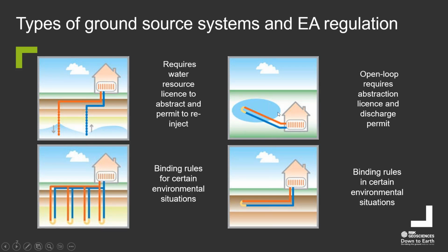Another type is water source, which could be a large lake, river, or even a canal. You can have either a closed loop or an open loop - abstracting water as before, or circulating a closed loop of fluid to extract heat from the water through to the heat pump. Open loop attracts the same regulation as the open loop borehole system. For closed loop systems you typically need several boreholes, circulating fluid through pipes to extract heat in a similar way - this example shows vertical boreholes, though horizontal schemes are also possible, as in the bottom right example, which needs a lot more land for the same heat output.